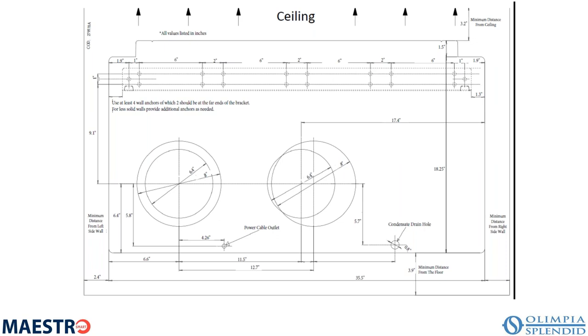The recommendation is to use the 8-inch holes whenever possible, but if you have a geometric constraint in your building or wall, you can use two 6.4-inch holes instead, with a small capacity and efficiency loss. If you can't get the 8-inch, it still gives you an option. There's also a 3/4-inch hole that you drill for the drain.